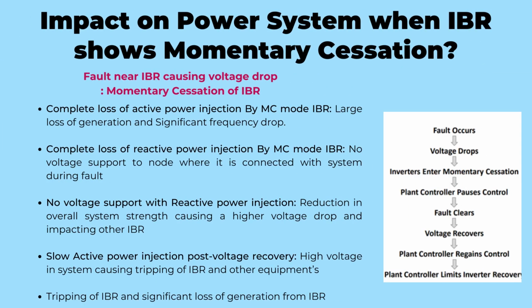The momentary cessation control mode in IBR has a significant impact on the overall power system. When IBR operates in this mode, there is a complete loss of active power generation, leading to a decrease in system frequency. Additionally, there is a loss of reactive power injection, which means that the IBR cannot provide voltage support to the nodes it is connected to during faults or disturbances. This reduction in reactive power weakens the overall system, causing a higher voltage drop and affecting the performance of other IBR units. Moreover, after a voltage recovery, the IBR resumes active power injection, but at a slower rate. This can result in high voltages in the system, leading to the tripping of IBR units and other equipment. Ultimately, the momentary cessation mode can cause the IBR units to trip during voltage disturbances, resulting in significant generation losses.